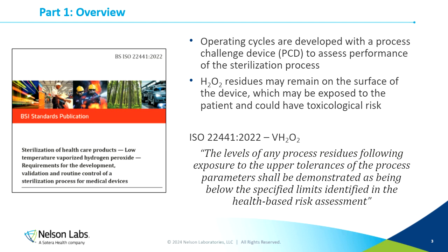So this standard has a statement about the peroxide residuals, and it says, "The levels of any process residues following exposure to the upper tolerances of the process parameters shall be demonstrated as being below the specified limits identified in a health-based risk assessment." I realize you probably read that far faster than I said it, but I just wanted to say that to show that it's kind of a mouthful, and it says a lot while also not saying very much specifically.